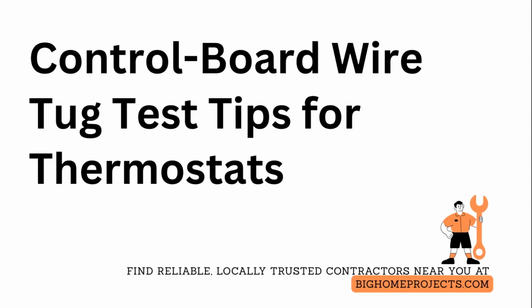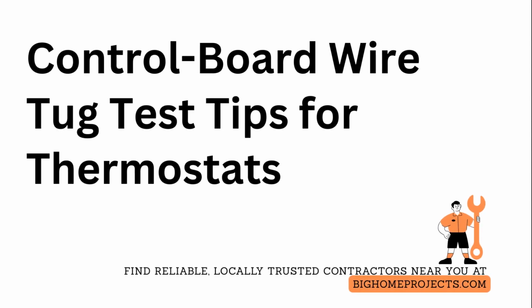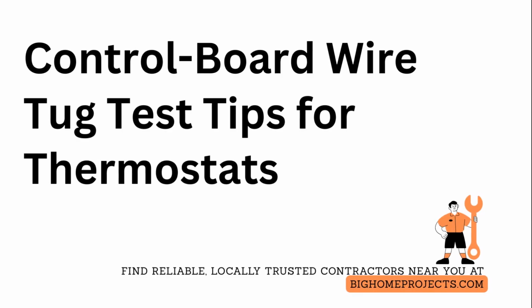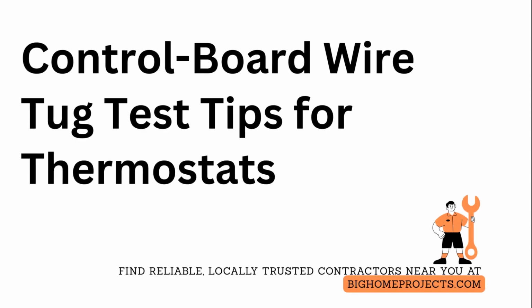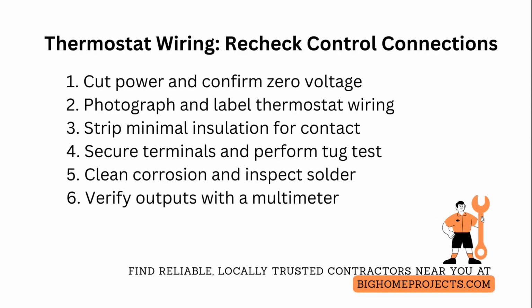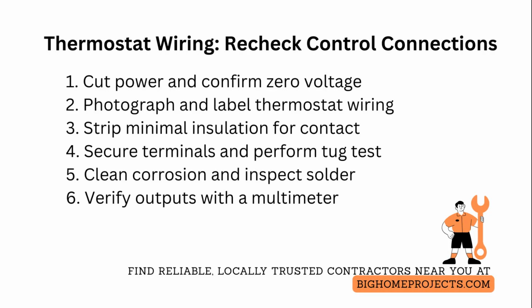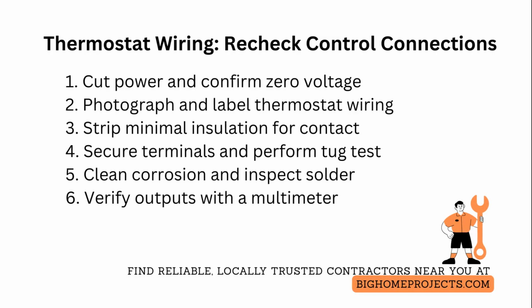Upgrade your thermostat. Recheck every control board connection immediately to prevent hidden failures and ensure long-term reliability. When replacing or upgrading a thermostat, start by cutting power at the breaker and confirming 0 voltage with a non-contact tester. Then remove the old stat and photograph the wiring for reference.